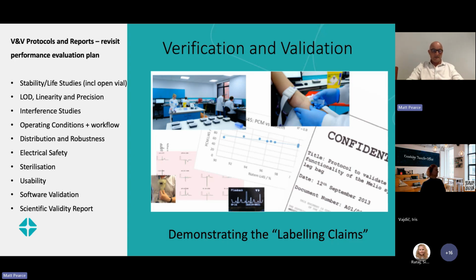So then you do the validation on manufactured product. So you test products that have been manufactured, usually multiple lots. So you'll test it to show that the product is stable over multiple lots. But you also do the reproducibility and linearity, limits of detection on certain types of technologies, interference studies. Interference studies is very important.